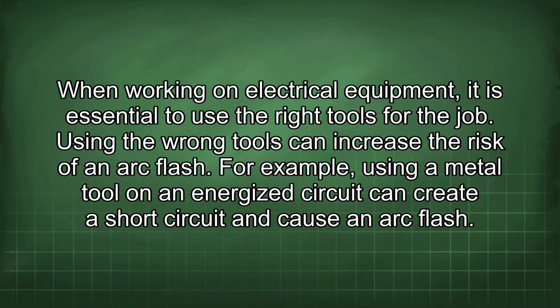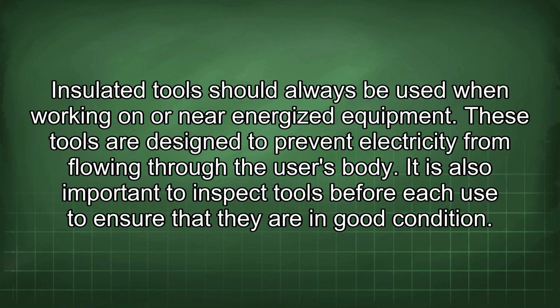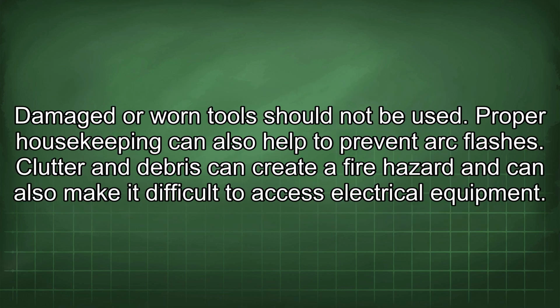When working on electrical equipment, it is essential to use the right tools for the job. Using the wrong tools can increase the risk of an arc flash. For example, using a metal tool on an energized circuit can create a short circuit and cause an arc flash. Insulated tools should always be used when working on or near energized equipment. These tools are designed to prevent electricity from flowing through the user's body. It is also important to inspect tools before each use to ensure that they are in good condition. Damaged or worn tools should not be used.